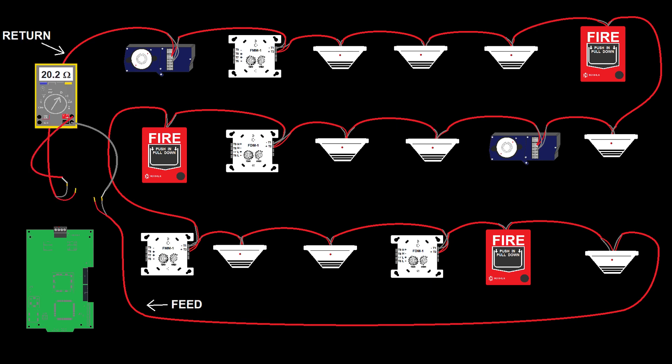The data signal can reach the devices on each side of the open. We will get a trouble on the panel letting us know that the loop has opened because it supervises continuity between the two negative legs of the circuit and between the two positive legs of the circuit, but all devices will still be able to communicate with the panel.